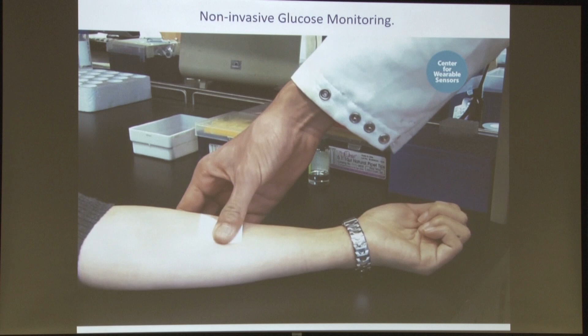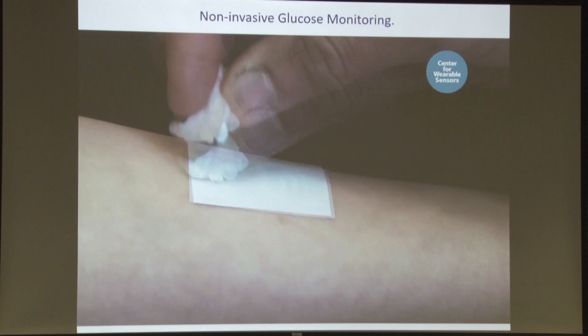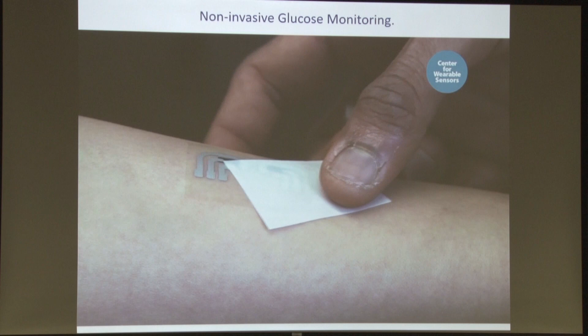And it's mostly for single use to replace the finger stick. So it's the same cost like a strip, but you don't do any finger stick blood. So again, this is a slow motion, and we'll place the electronic here, which is reusable. So with this, you can obtain, again, before the meal, after the meal. It takes a total of 2 minutes, 90 seconds of iontophoretic extraction, another 30 seconds of the detection, nice correlation to blood glucose meter. So it's a single use.